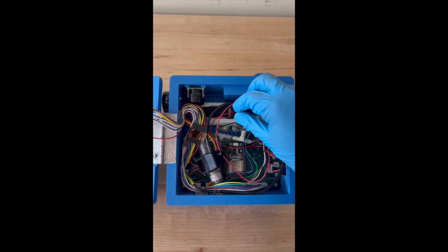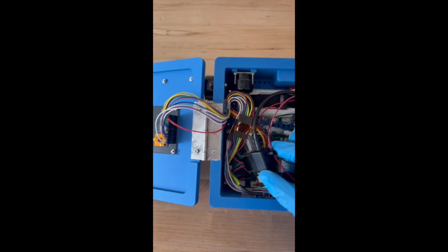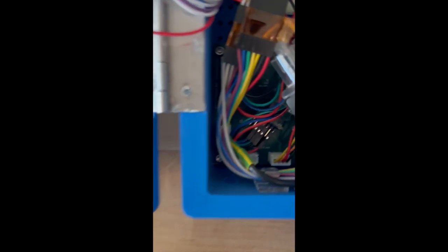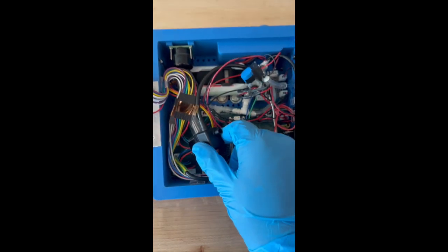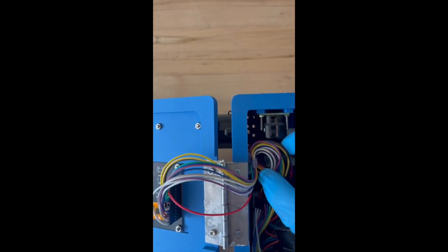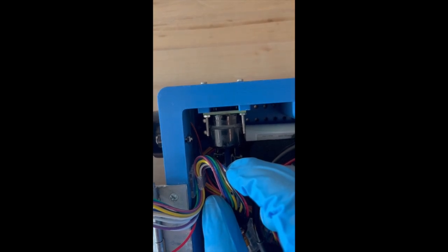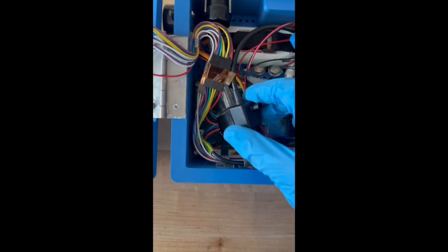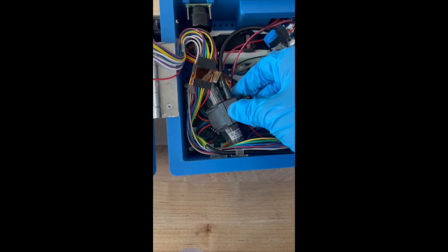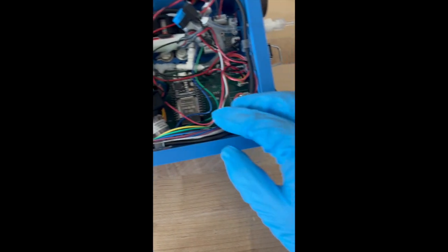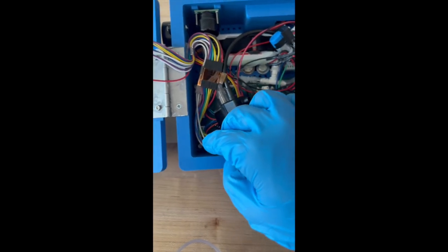After this relative humidity and temperature sensor, we are then going to the absolute pressure sensor, so we can do pressure compensation and enable more accurate readings of CO2 according to higher pressure in the line or different altitude levels. Then we go to the actual CO2 sensor, which works through non-dispersive IR sensing, and finally the flow sensor, which enables us to tell if the sample line is blocked.